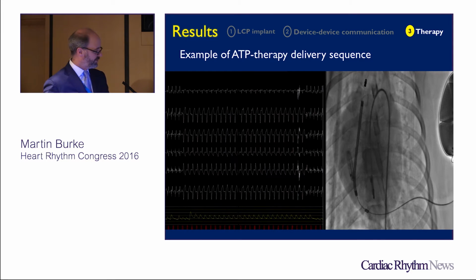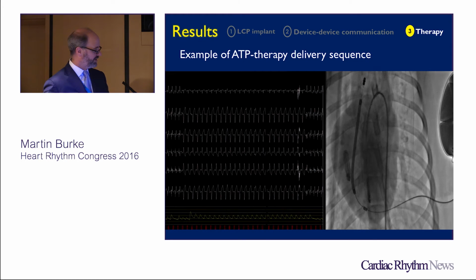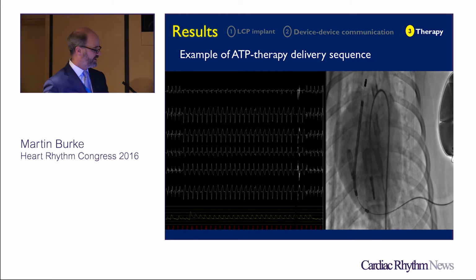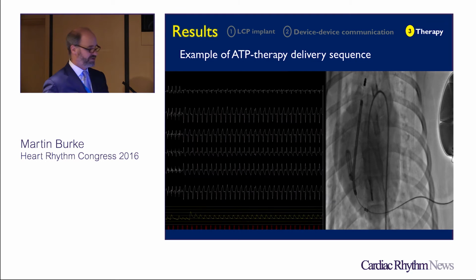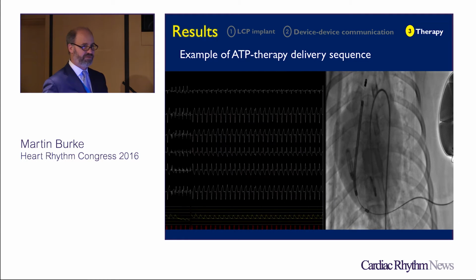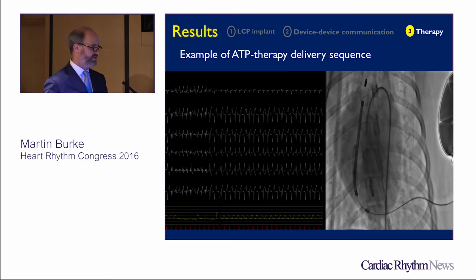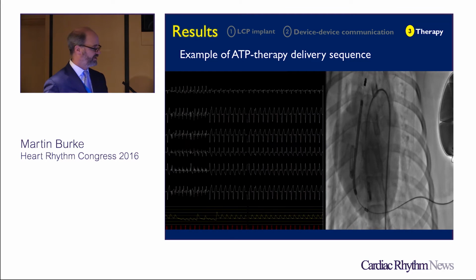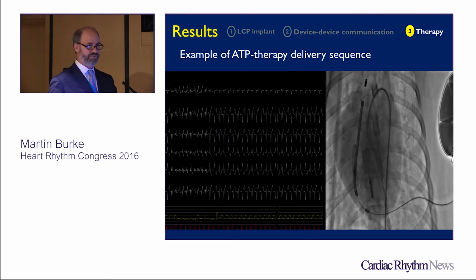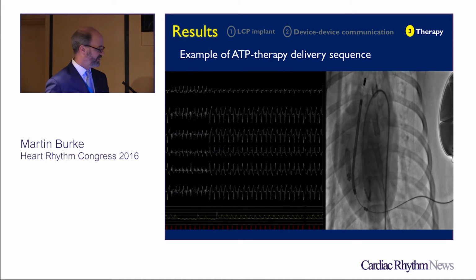And the communication is quite stout, and you can actually see capture on a high level. There's no dysfunction in the sensing consequent to the communication. So the device is still sensing and still delivering automatically in a series that you might see if you program on this series of ATP.